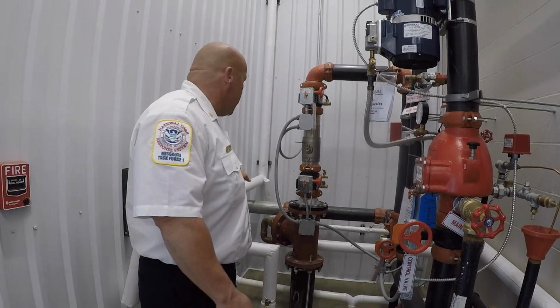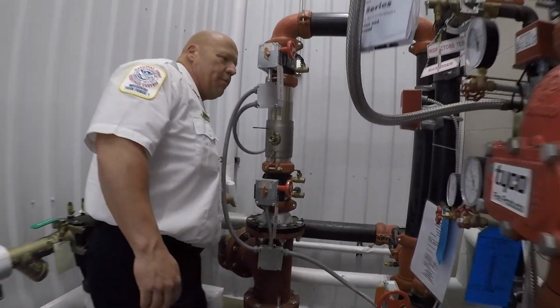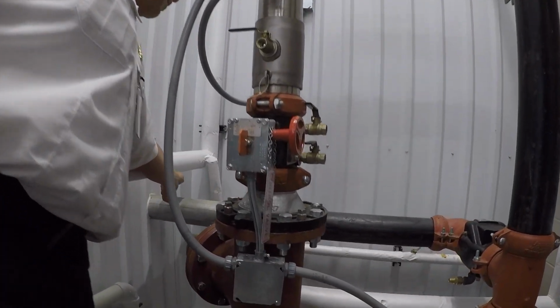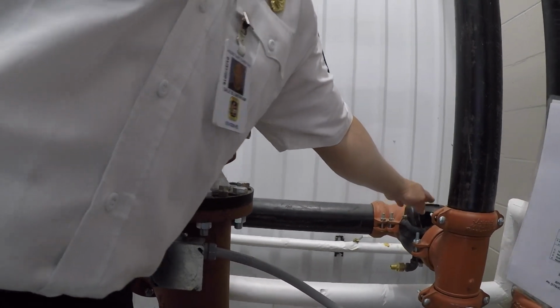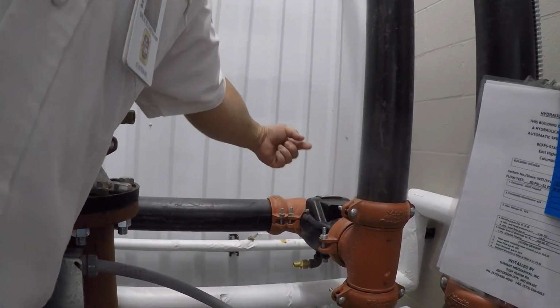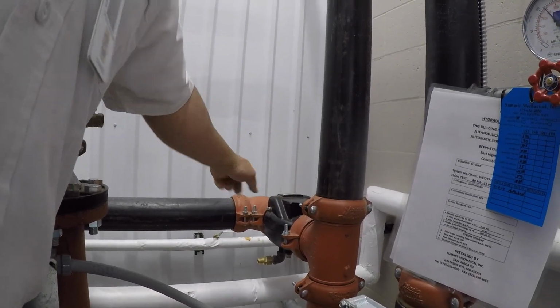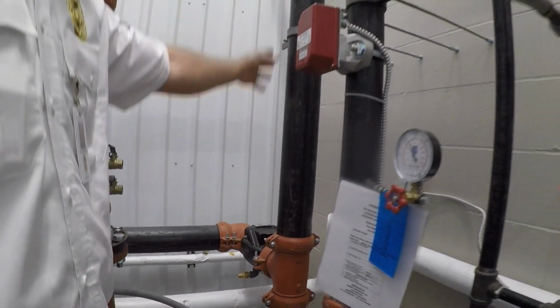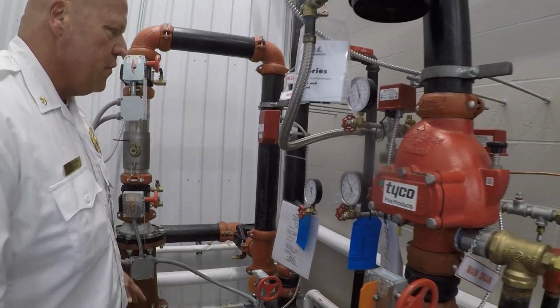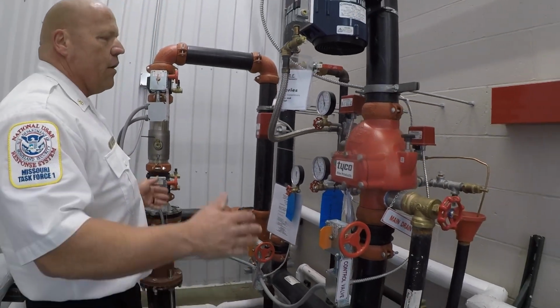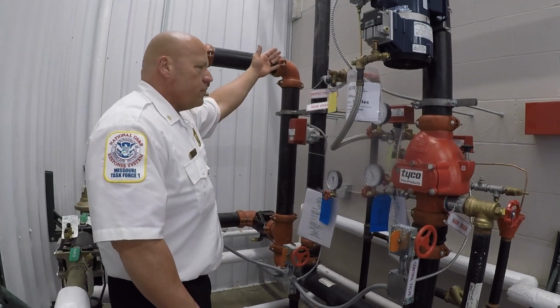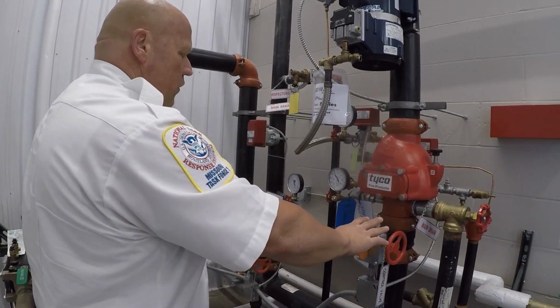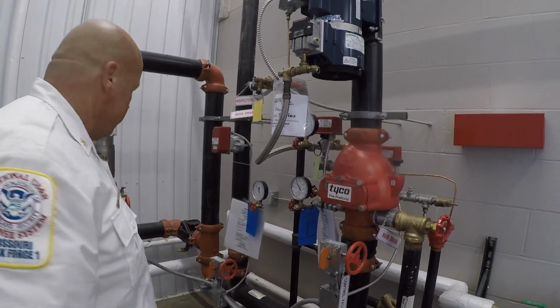So the fire department connection, as you can see, this pipe goes through the wall, so that's where it comes in. This is a one-way valve that only allows water to come into the system, not flow back out. And so this is where you're supporting your sprinkler system. This system right here has 2 different systems on it. It has a wet system and it has a dry system. So we're going to talk about how that works.